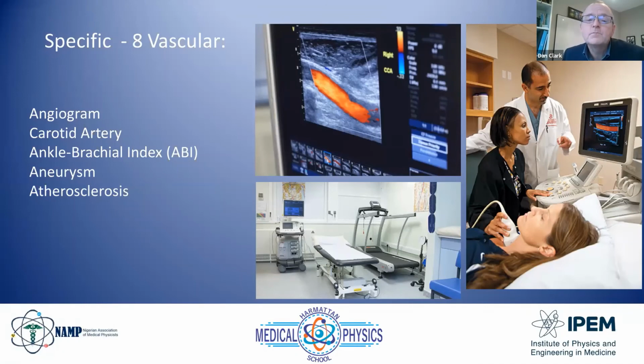The second thing it's doing is it's measuring the Doppler shift. So it's sending a sound wave into the body. Some of that will be reflecting back up off moving blood corpuscles, red cells in the artery. And because it's reflecting off a moving body, the frequency of the reflected sound is slightly different, and we can see that shift in frequency, that Doppler shift. And you've probably come across the Doppler shift in some of your work in your universities. That Doppler shift enables us to tell the speed that the blood corpuscles are moving.